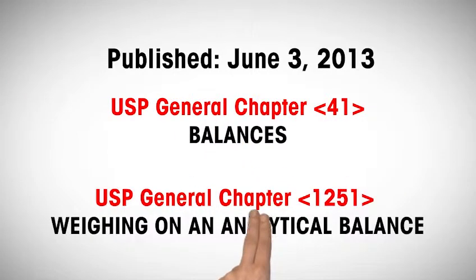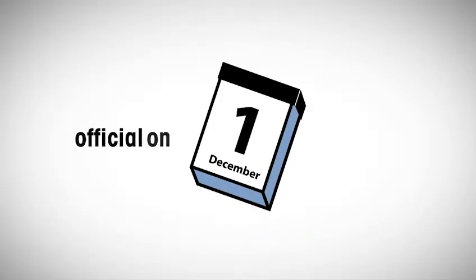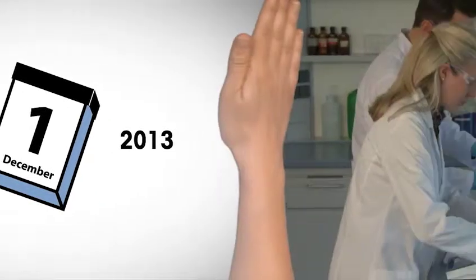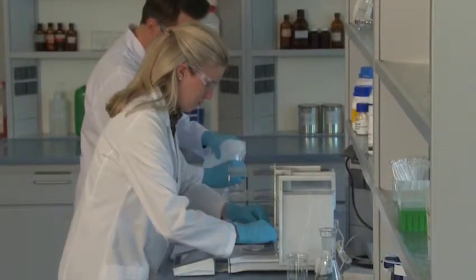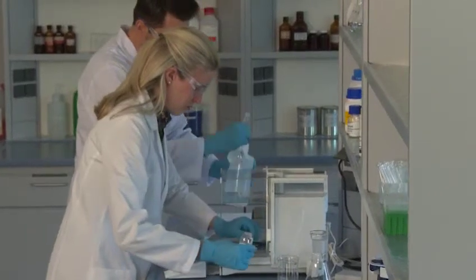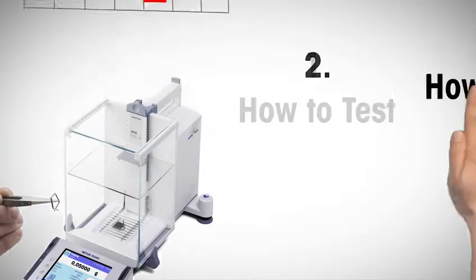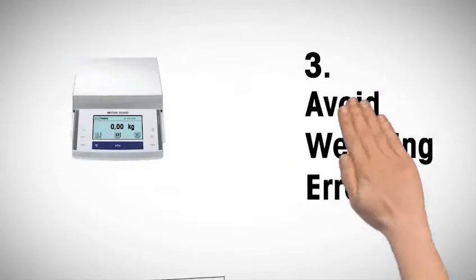On June 3rd, 2013, the United States Pharmacopoeia has published a second supplement to the USP 36 National Formulary 31. This video informs you about the relevant changes in the general chapters about weighing, namely USP General Chapters 41 and 1251, which will be official on December 1st, 2013. I'm going to show you the implications of these new chapters for the quality management of balances in 3 parts: how to test the weighing equipment, how often to test it, and how to avoid weighing errors.